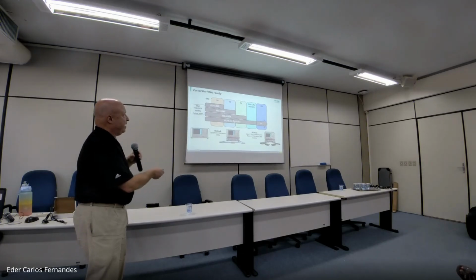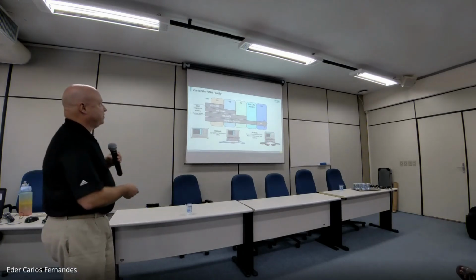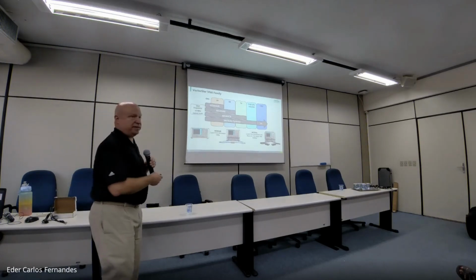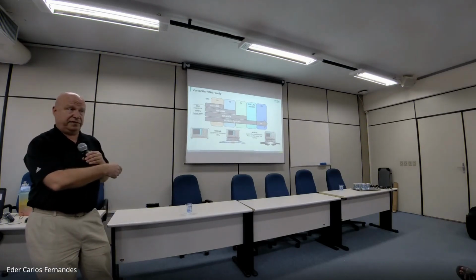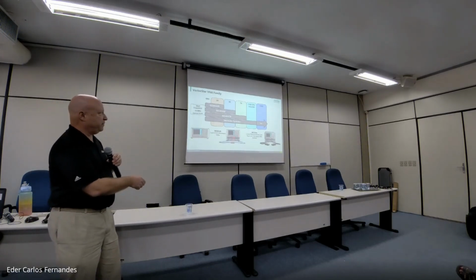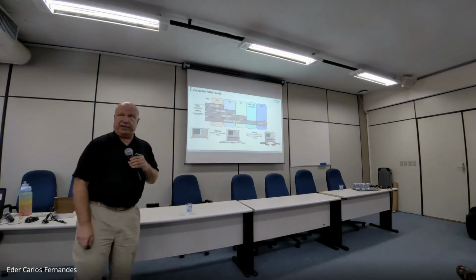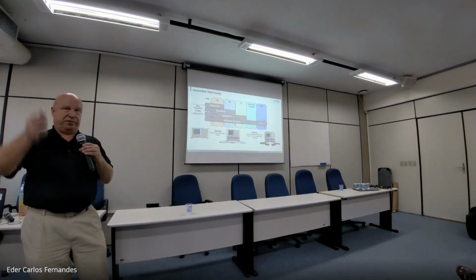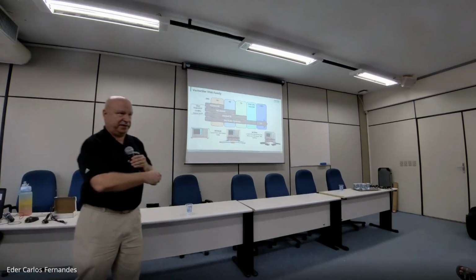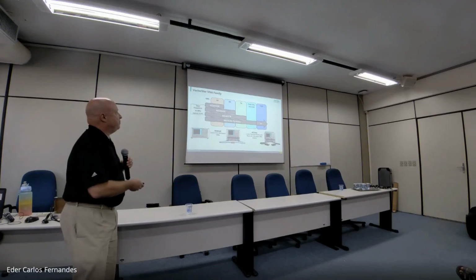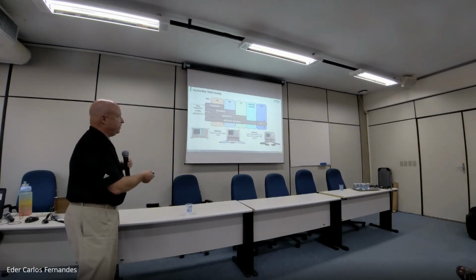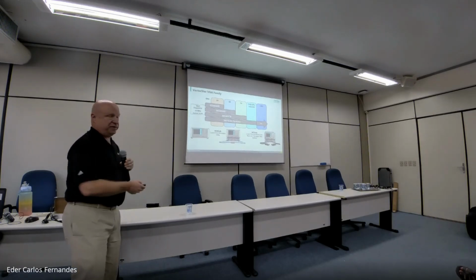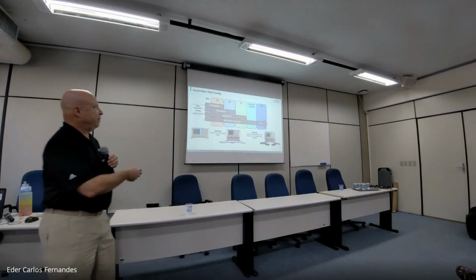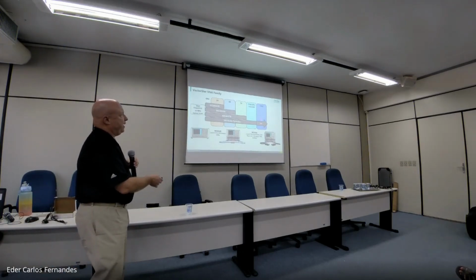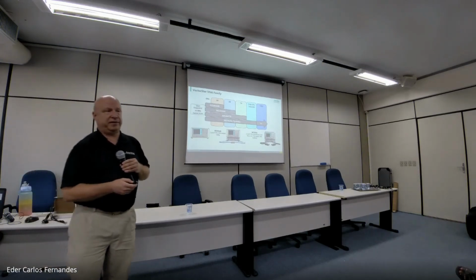Then we can add extender modules like these and the test set that provides the RF and LO to the modules and allows us to get up to as high as 220 gigahertz. So everything that I show you here is building blocks. You start with this basic unit, you add a test set to expand to 4 ports, or you add a test set to expand to millimeter wave broadband, or you combine them all together and make a 4-port broadband system. So everything is possible here. There are no upgrade paths that can't be accommodated. Now, above 220 gigahertz, where we have our single sweep systems, we have the banded ranges up to 1 terahertz. So the system here at Unicamp has the single sweep 220 plus 2 bands to get to half a terahertz, 500 gigahertz.